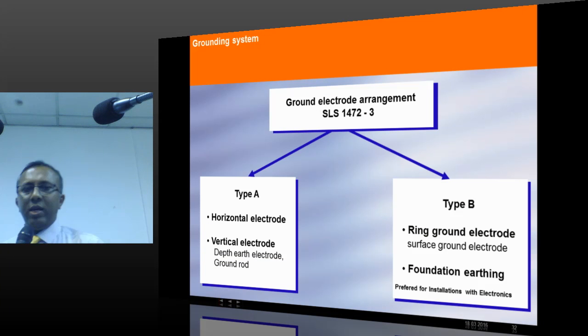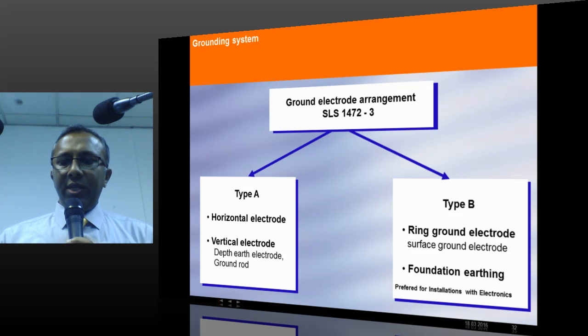Now we go to down conductors, earth termination. There are two types of earth termination explained in the standard, type A and type B. Type A is isolated from the building, maybe a vertically driven rod or a horizontal conductor, a horizontal electrode or a vertical electrode. Type B is a ring ground electrode and foundation electrode. So for buildings with electronics, this is the only recommended way. Type A is recommended for small houses or small buildings without electricity connection. How many buildings can we see without electricity connection? Almost nil. So generally, this is what is required. Type B, either a ring conductor or a foundation earth electrode.